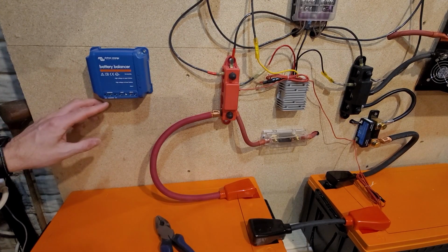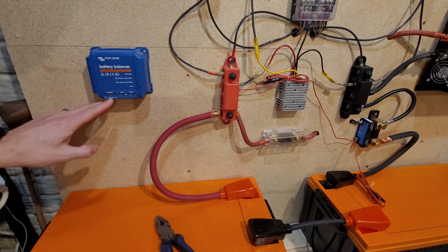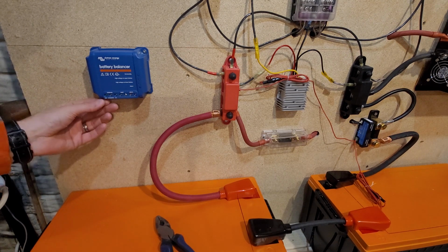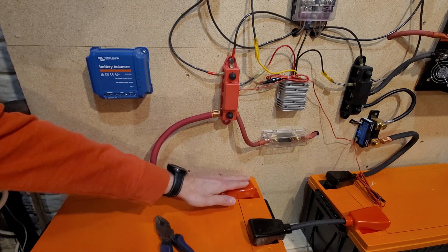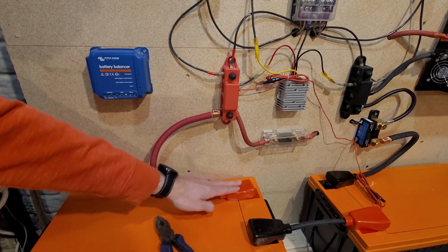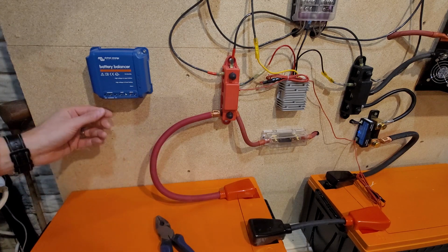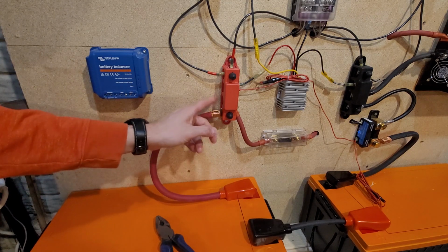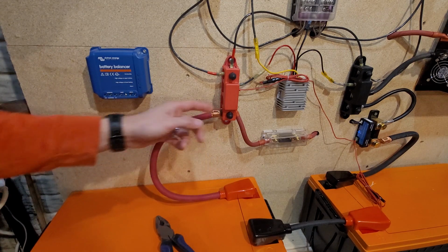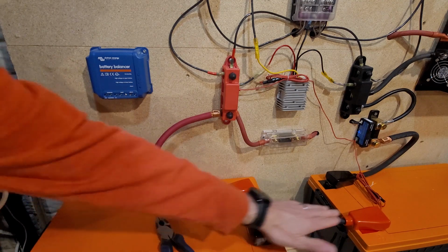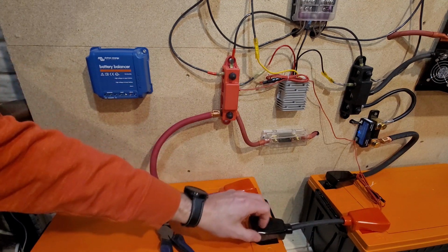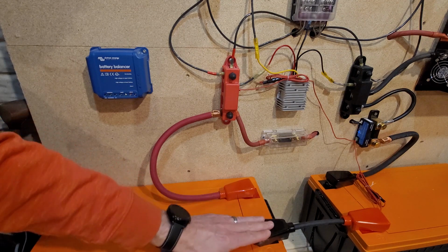On this battery balancer, there is a 24 volt, a common, and a 0 volt. And these connections, the 24 volt is going to go to the farthest positive. So what I'm going to do is connect the 24 volt right to my bus bar. The common is the bridge in between the two batteries. So I'm going to connect it directly to this negative side right here.